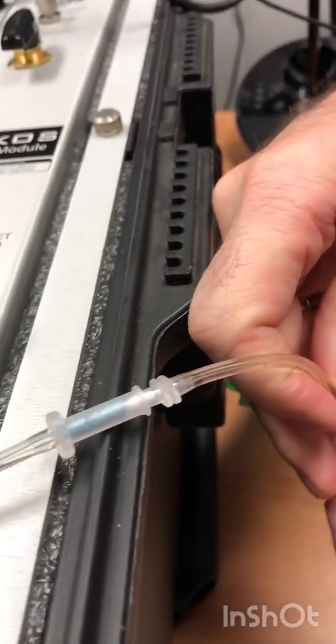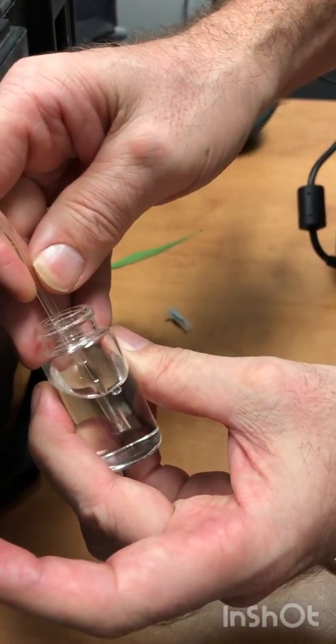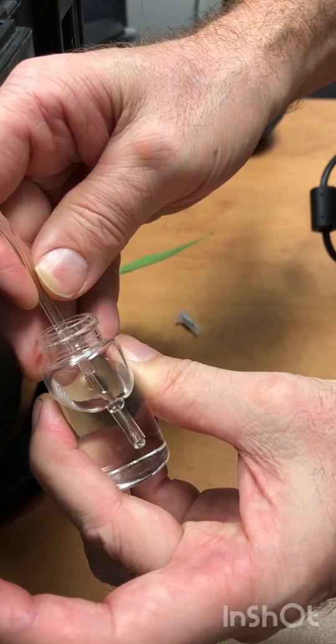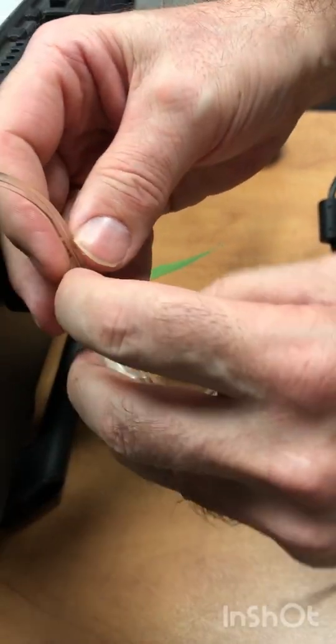Test each of those outlets to make sure that there's a flow of gas. Now I'm testing channel B green, and again there's a steady flow of bubbles. You do all of them — the two green and the two red. In normal operation of a Myrkos you should see bubbles for each of them.